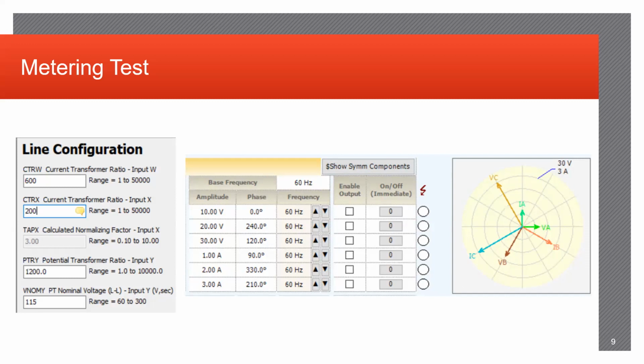So for example, before you set up your test set's configurations for the values, you want to identify that the basis and settings information that you receive from the protection engineer correctly matches up with what the ratio is going out to the equipment.